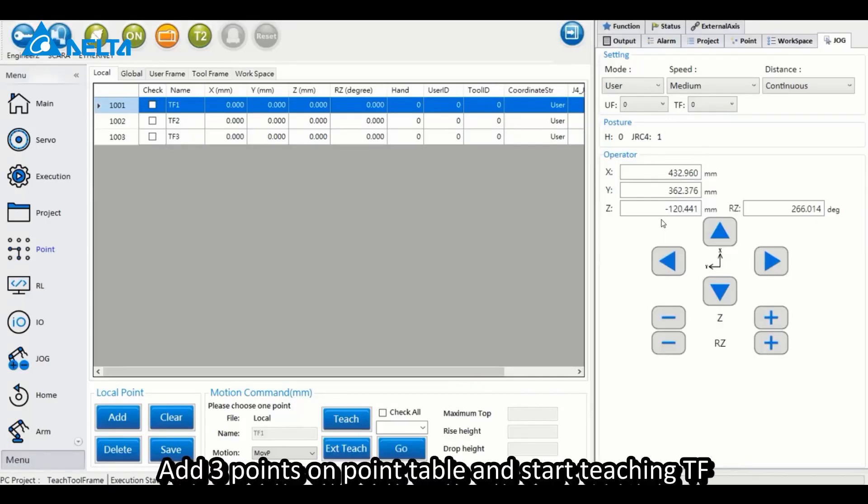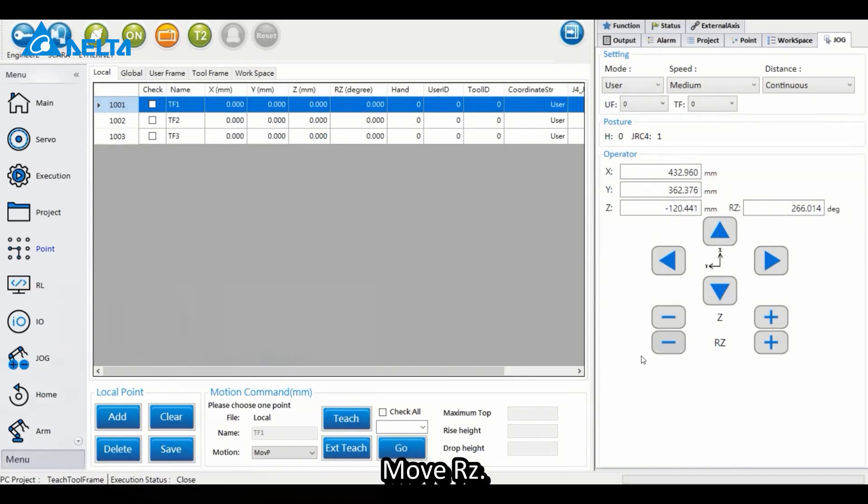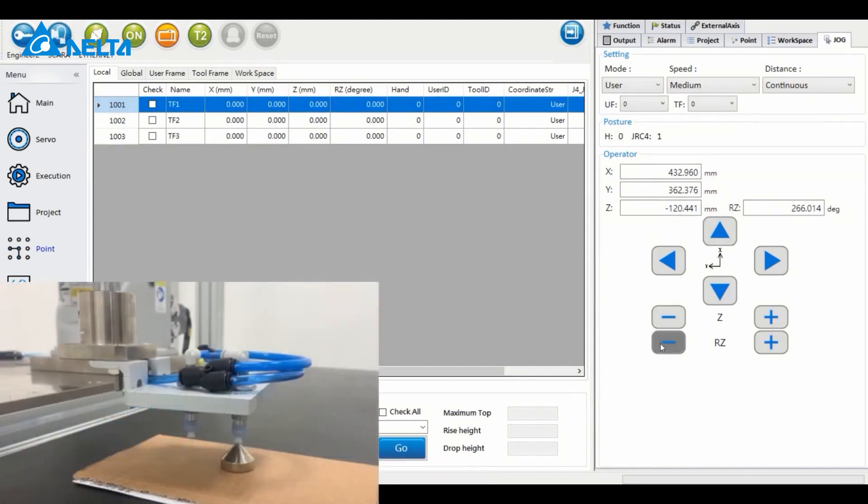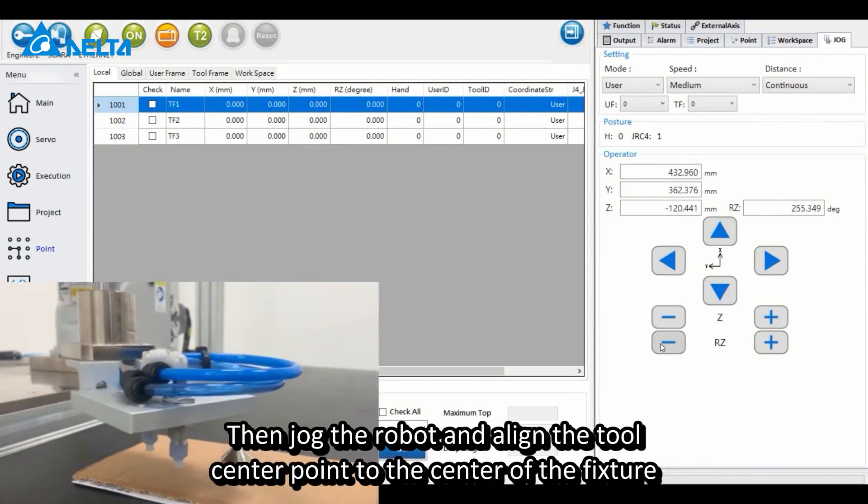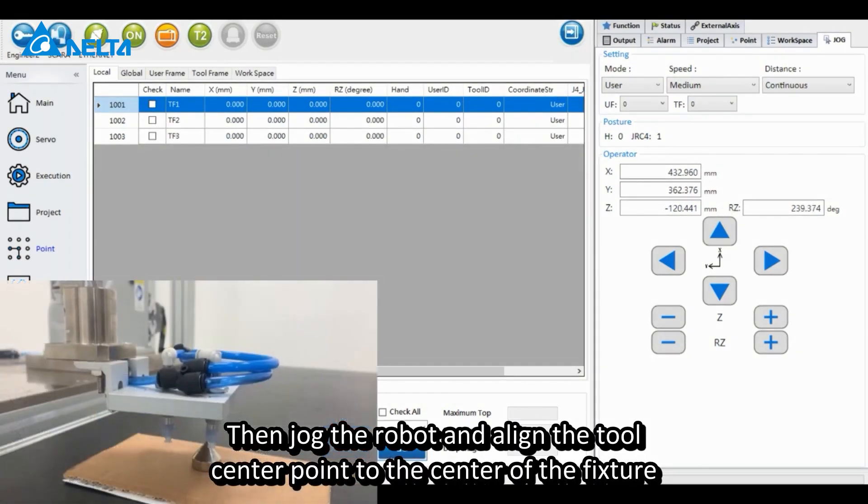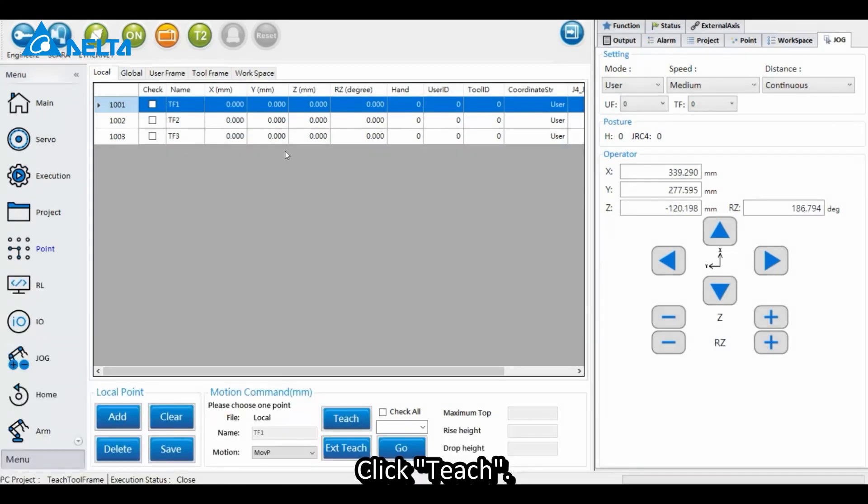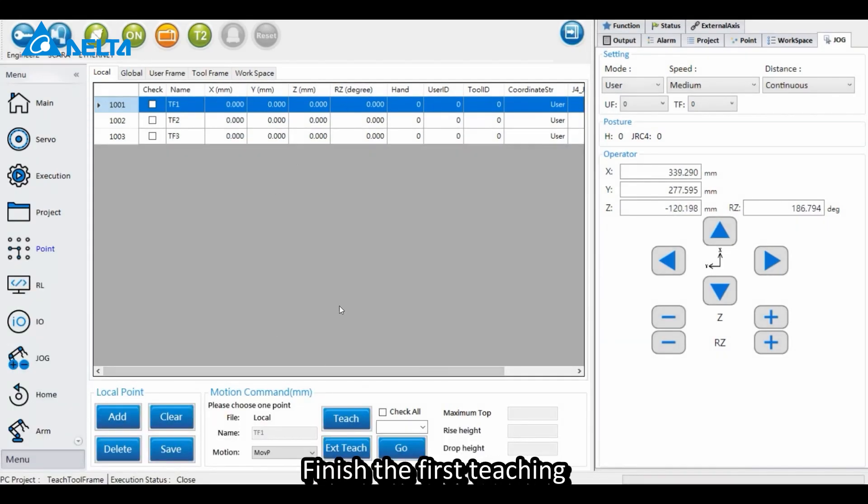Add three points on the point table and start teaching TF. Move RZ, then jog the robot and align the tool center point to the center of the fixture. Click Teach to finish the first teaching.